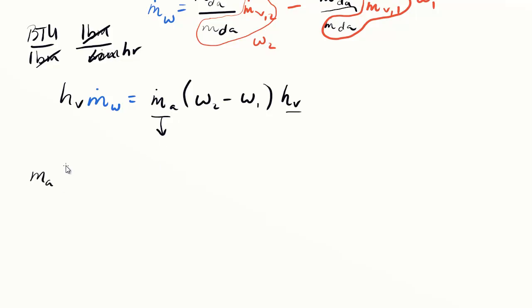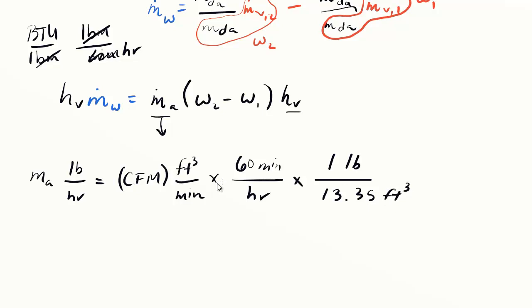The mass flow rate of air in pounds per hour is equivalent to a CFM value, feet cubed per minute. We need to get from feet cubed per minute to pounds per hour for air. There are 60 minutes per hour, and at standard air conditions, we have one pound of dry air per 13.35 feet cubed. Canceling units, what's left over is the CFM value multiplied by 4.5.